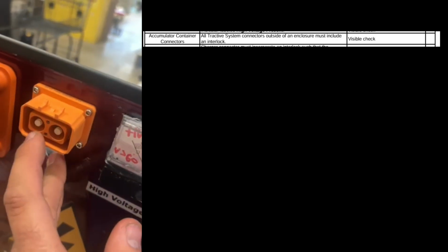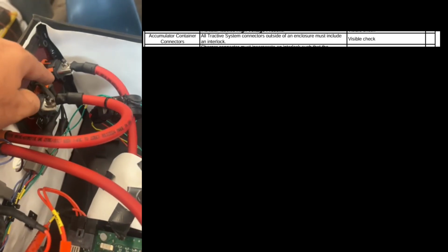Our main connector coming out of the pack is right here. It has an interlock that you can see here, and on the other side of it for these blue wires. The energy meter also has an interlock right here, and our MSD has an interlock which is right here. On the other side, there are 2 pins, the interlock pins.